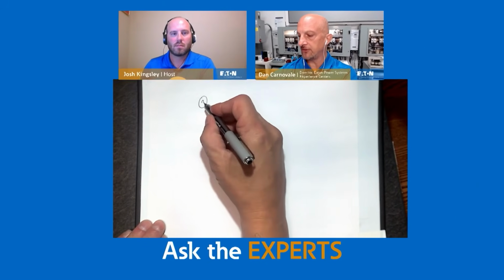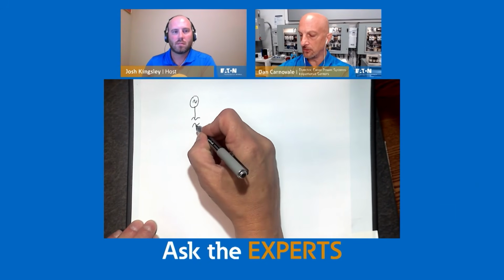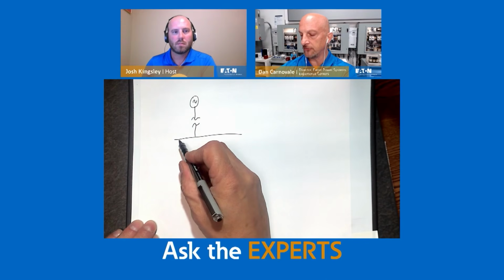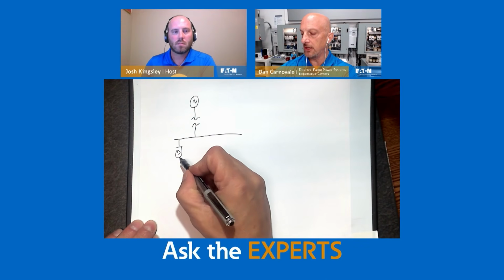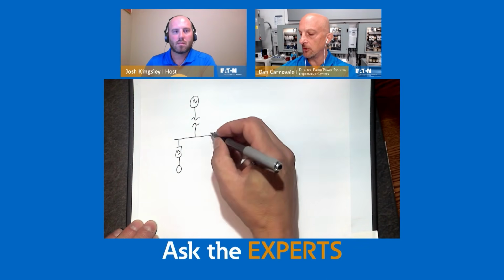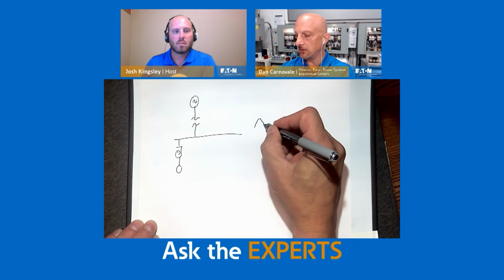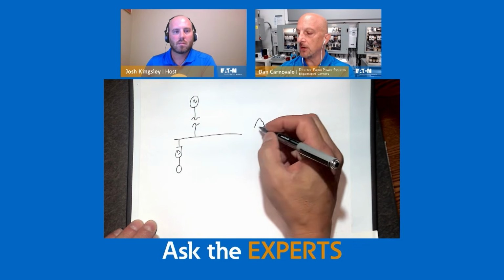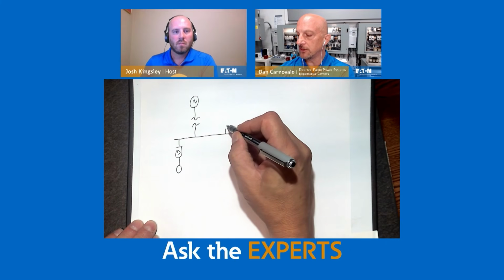So one of the things that we addressed in the paper was the whole individual drive approach versus system approach. And that really does go into those kinds of things. And again, it's a technical and economic choice. I'll show you an example here. So if I have my source and my transformer, and again, I'm running this as a simplified case, but if I have a bunch of drives here and I'm creating some harmonic distortion, and I start to mess up my voltage distortion here, and maybe I want to transfer over to a generator.